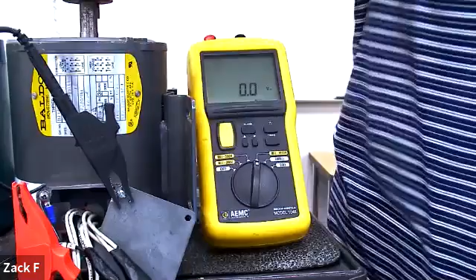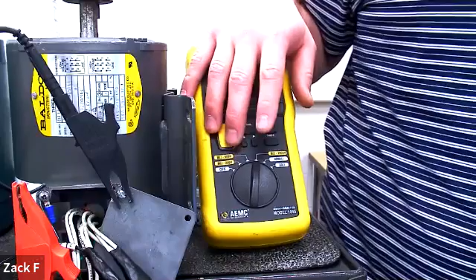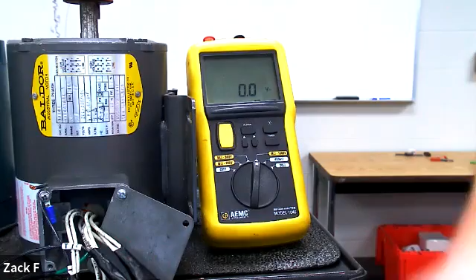What if you're using a megger, not checking motor windings, where do you put your leads in that case? I've checked underground with it. If it's underground and in a conduit with water, or even direct buried, there's going to be some kind of moisture in there. So wherever you're checking it, in a cabinet or panel or whatever, you're going to have a good ground, something going to a ground rod, a grounding electrode conductor. That's where you'd put one lead, and then this would just go on whatever conductor you're trying to see. You want to make sure that's disconnected from the circuit.